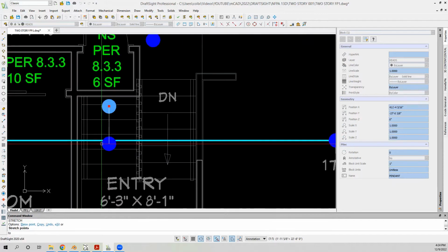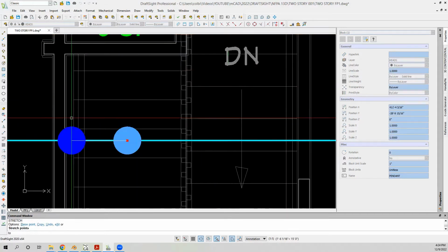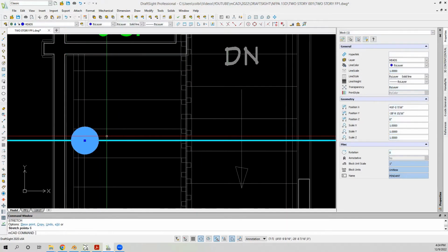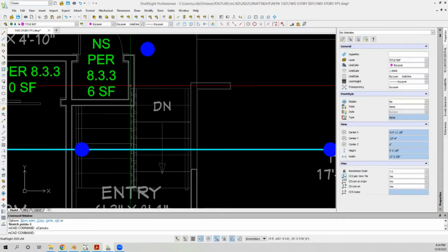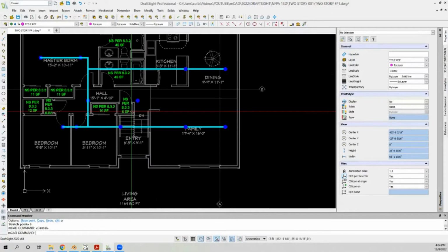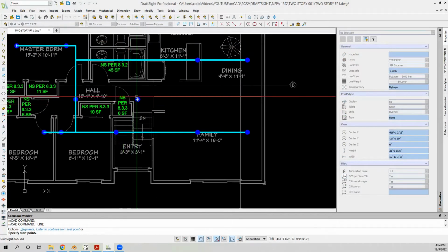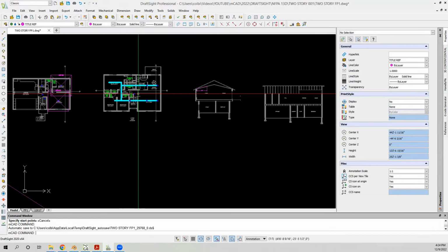What about if I just actually do this? Six inches off that wall. There's no direct line of sight between these heads, so they're not going to interfere with each other, with the spray patterns. All right, I need to connect this one here. Let's see. I'm going to wait for that.